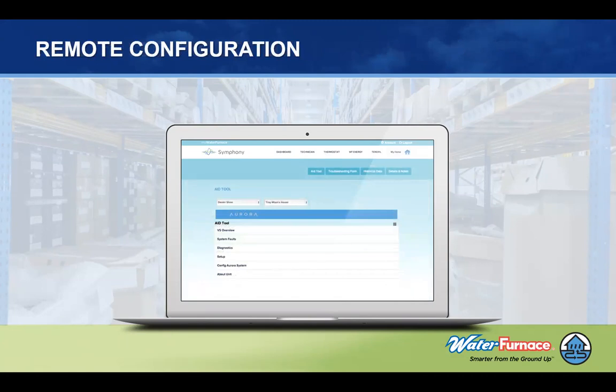And then we can do remote configuration. So if it is a parameter within the system that we can configure, we can go into Symphony Remote and do some system configuration. So for example, a lot of calls just after startup are nuisance calls where we didn't quite set up the system correctly. Maybe we have too much airflow going to a bedroom or something like that. We can go into the system and change the fan speeds from the variable speed fan motor, all because we have a communicating system that changes parameters back to the unit level, and we don't even have to travel back to the job in order to fix that issue. We can do it remote.